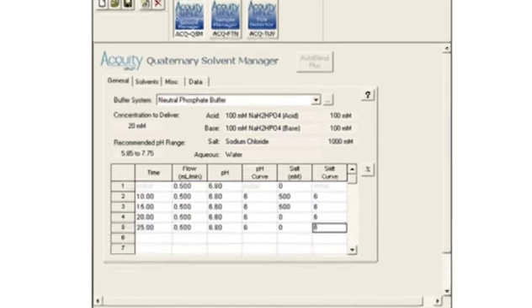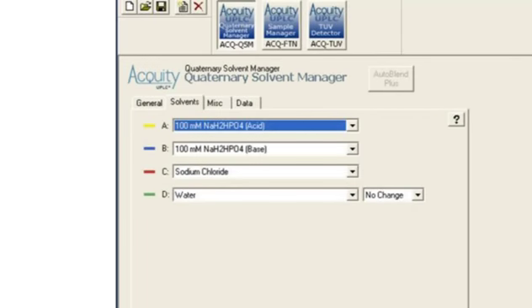We have considered how to create a buffer system that will be used to calculate the proportions of each solution to be delivered during the separation. Our last obligate task is the association of the defined acid, base, salt, and aqueous solutions with particular solvent lines and proportioning valves. From the main solvent manager instrument method, choose the solvents tab. The solution placed in each of the four solvent reservoirs is now selected from the drop-down. This function for assigning different physical reservoirs to the specified names becomes very important and valuable when the system is configured with a six-port solvent select valve. This valve is always associated with the D reservoir, which can then be used for various acids, bases, or salts. The specific D line is selected from the drop-down menu to the right of the solvent selection box.